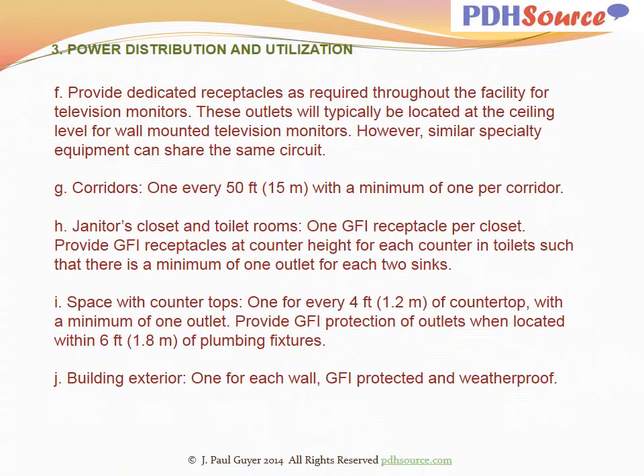Provide dedicated receptacles as required throughout the facility for television monitors. These outlets will typically be located at the ceiling level for wall-mounted television monitors. However, similar specialty equipment can share the same circuit. Corridors, one every 50 feet with a minimum of one per corridor. Janitor's closet and toilet rooms, one GFI receptacle per closet.